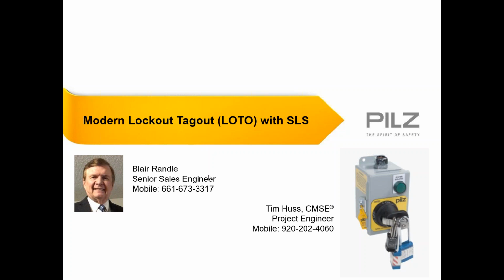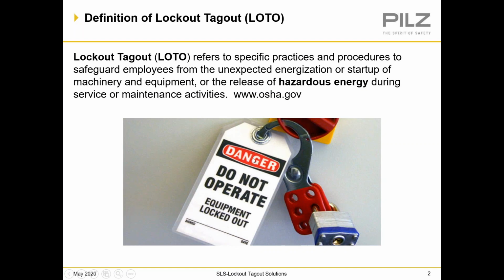We're going to talk about our SLS system today, which is used for lockout and tagout. But before we do that, we want to define what lockout tagout is. As OSHA defines it, lockout tagout has two features. One, it is used to prevent unexpected startup of the equipment by having power reapplied without being controlled. And secondly, it is used to remove hazardous energy from a zone where it normally is being applied when there are people in that zone doing service work. Those are the two main characteristics of lockout as OSHA defines it.